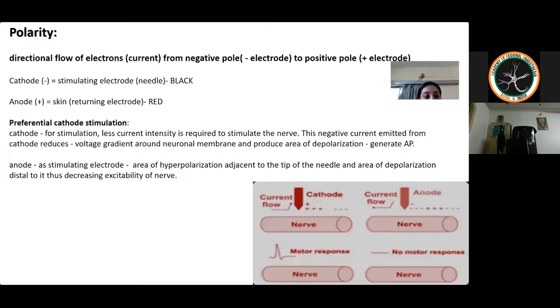Now here, the stimulation should be done only by the cathode. If we use the cathode for stimulation, we require very little current to stimulate the nerve. That means the negative current which flows from the cathode will reduce the voltage gradient around the membrane and will produce depolarization and generate an action potential. So it's easier to stimulate the nerve and there is less discomfort to the patient, as the current required is very low.